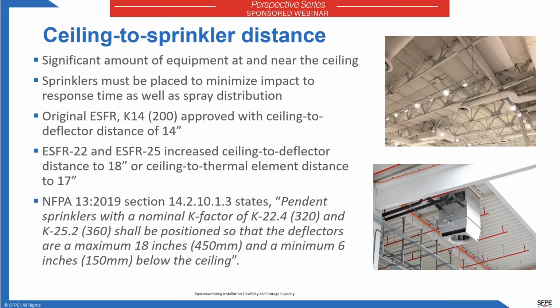And NFPA 13 states that sprinklers with the K factor of 22.4 and 25.2 shall be positioned so that deflectors are a maximum of 18 inches and a minimum of 6 inches below the ceiling. So going from the 14 to the 18, we increased the distance by about 4 inches or so. And that's actually pretty significant in dealing with what's on the ceiling. So the pipes on the K25 and 22 can be lowered if needed. The sprinklers can be lowered if needed or moved around with greater flexibility. And that, a few inches may not seem like much, but for the trades, having as much flexibility or having any flexibility is a good thing.